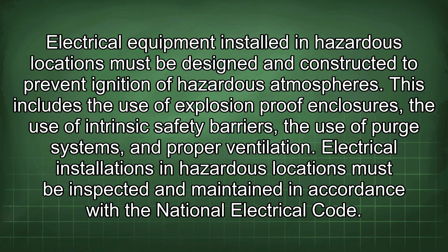Electrical equipment installed in hazardous locations must be designed and constructed to prevent ignition of hazardous atmospheres. This includes the use of explosion-proof enclosures, the use of intrinsic safety barriers, the use of purge systems, and proper ventilation. Electrical installations in hazardous locations must be inspected and maintained in accordance with the National Electrical Code. This includes proper grounding, protection from corrosion and heat, adequate ventilation, and proper bonding and sealing.